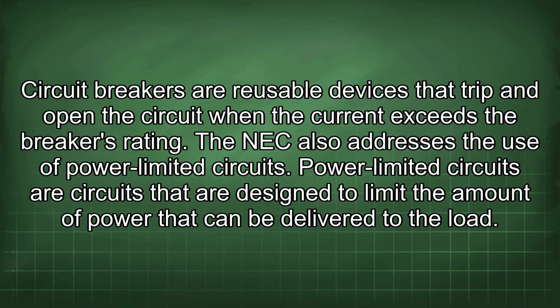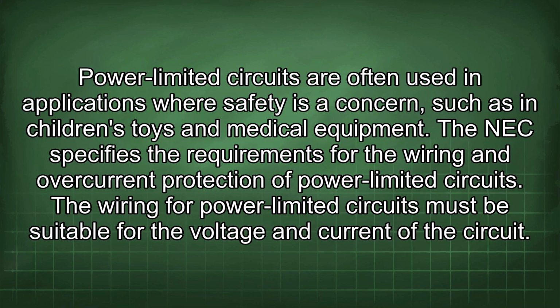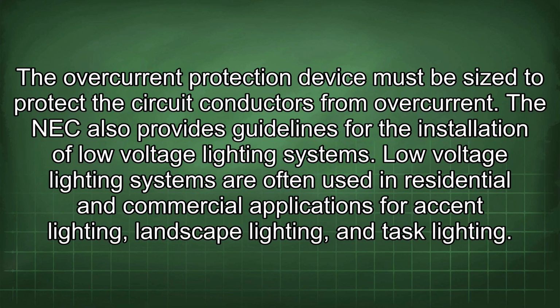The NEC also addresses the use of power-limited circuits. Power-limited circuits are circuits that are designed to limit the amount of power that can be delivered to the load. Power-limited circuits are often used in applications where safety is a concern, such as in children's toys and medical equipment. The NEC specifies the requirements for the wiring and overcurrent protection of power-limited circuits. The wiring for power-limited circuits must be suitable for the voltage and current of the circuit. The overcurrent protection device must be sized to protect the circuit conductors from overcurrent.